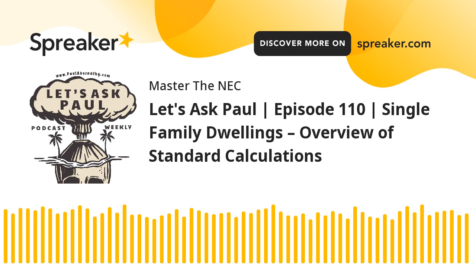Now, interesting. Once we do that, then we have to determine what's the minimum size of the service that we're dealing with here. So if those conductors came back at, I'll just throw a number out there, 193 amps, and I had to have conductors good for 193 amps. Well, before we even start looking for conductors, and I'm going to show you what we might be able to do in 310.12, the first thing you're thinking is, okay, I get it, but I have to size the protection first. Because once I establish the protection, then I can use what we call the 83% rule if it's applicable. But I still have to do it.